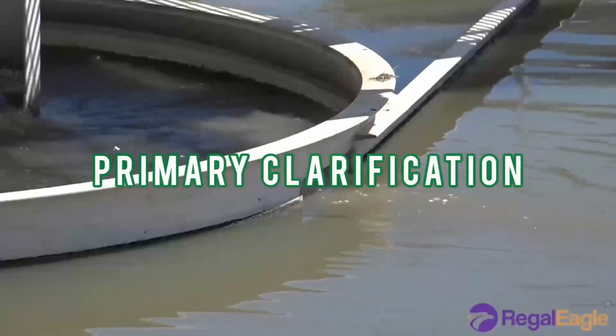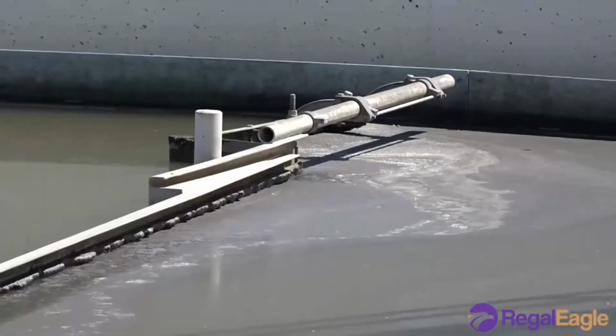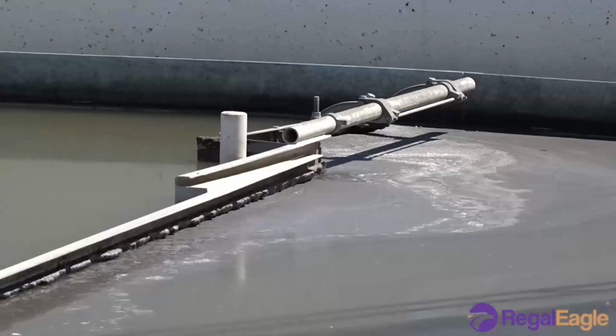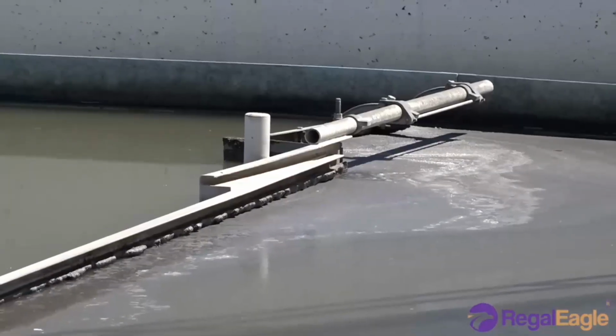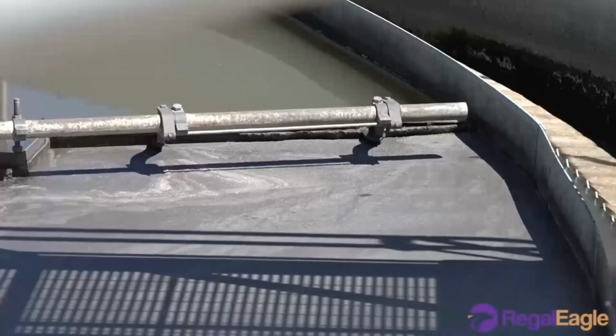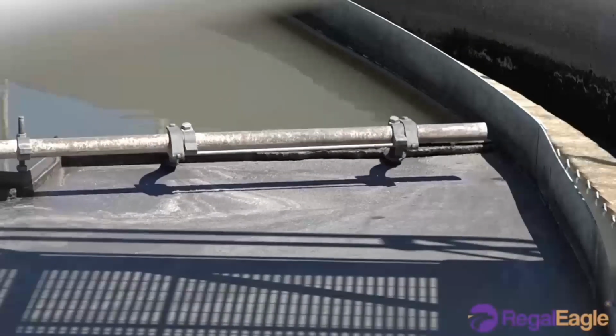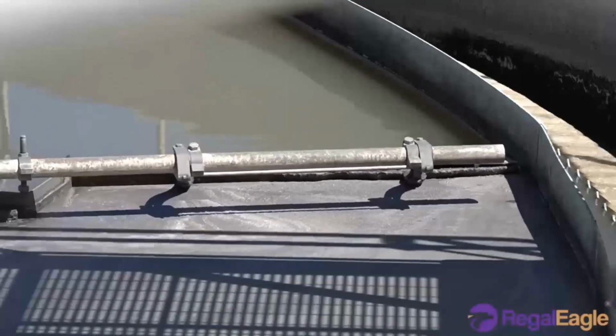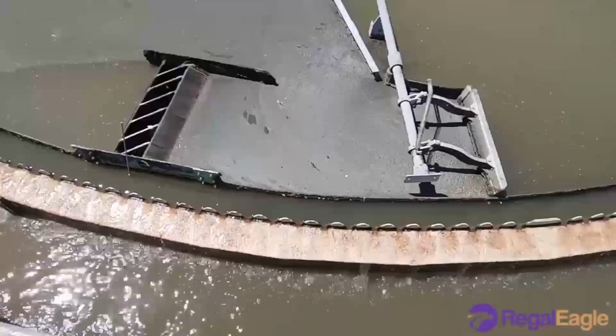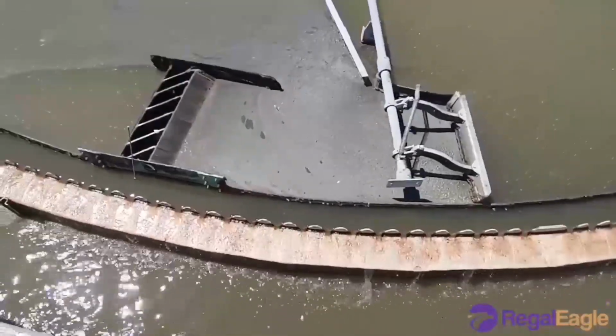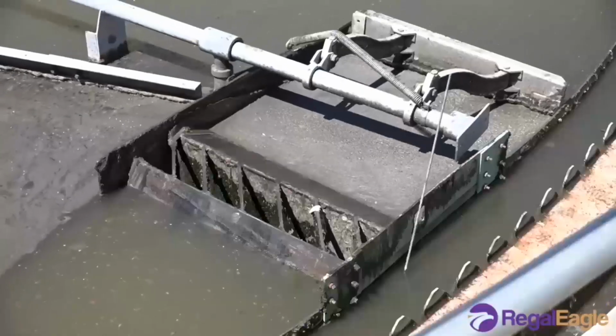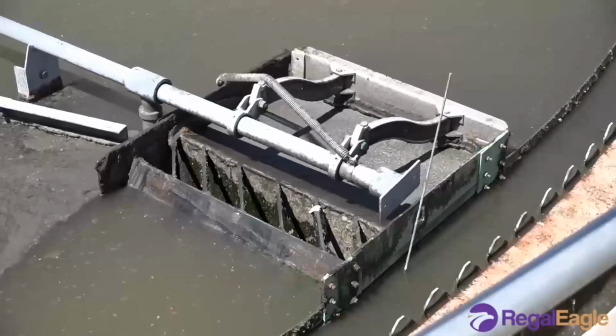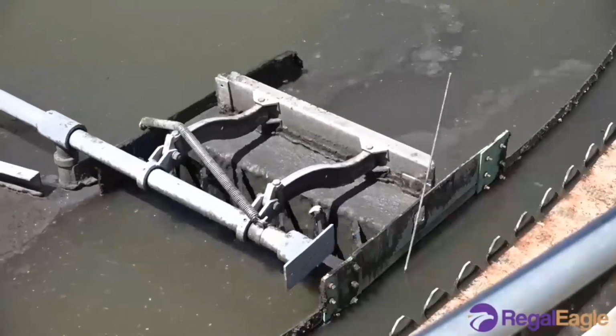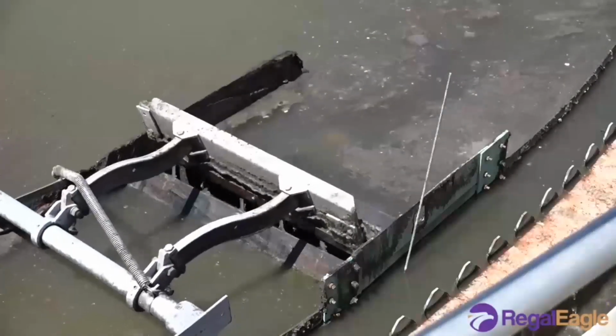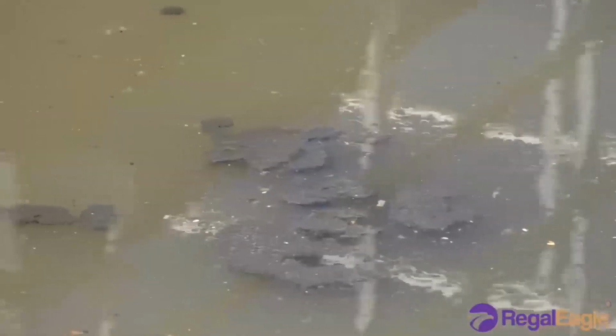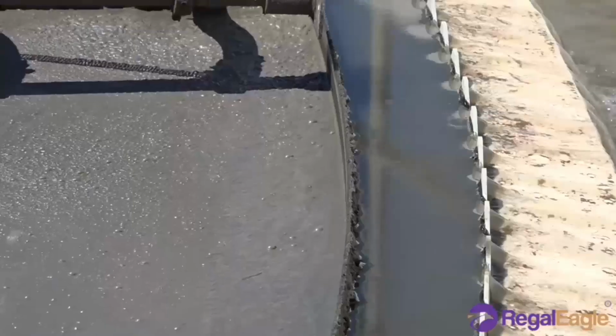Primary clarification, also known as sedimentation, is the first step in the water treatment process for removing suspended solids, oil, and grease. During this step, solids floating at the surface and other large particles from the water or wastewater flows are removed before biological treatment. Sludge is settled to the bottom of the clarifier basins and collected by a rake and removed by a sludge removal system. Meanwhile, oil and grease float to the surface and are skimmed off.